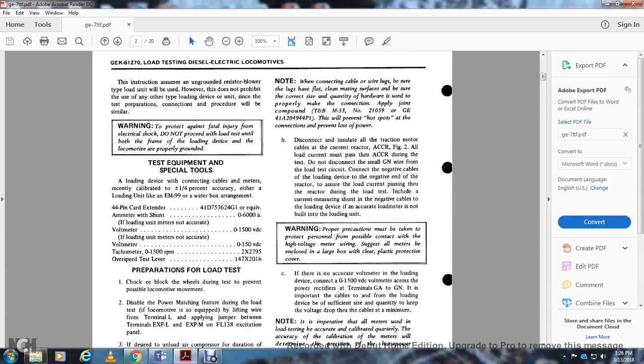Note: when making the connection, be sure the cable lugs have flat and clean mating surfaces, be sure of the correct size and quantity of hardware, and apply the joint compound properly to the connection. This will prevent a hot spot at the connection and prevent loss of power.